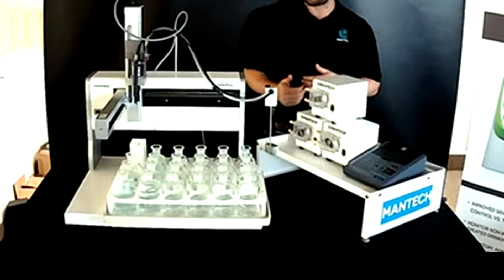And then you have your auto sampler, which is really doing all of the hard work, I guess you could say: moving the probes into the bottles, automatically going in there, turning on a stir, which is located directly on the probe itself, and reading that DO. If you have this fully automated system, before it reads the DO, it can do that sample preparation for you. So it'll add the dilution water, it'll add the seed and the inhibitor at the right time, and then finish filling up that dilution water. It actually uses a liquid level sensor, which brings that right up to the neck, exactly where it needs to be, calculates precisely how much was added, and then it goes in and measures the DO.